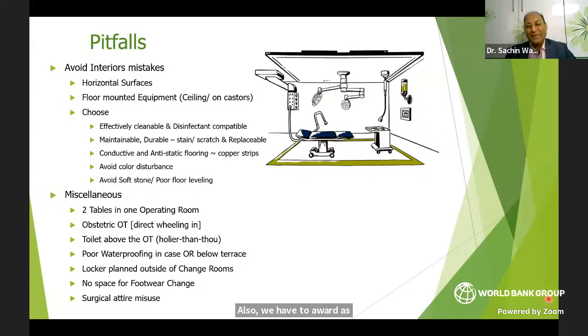We also have to avoid, as much as possible, floor mounted equipment. So primarily all equipment will be either ceiling suspended, like the OT lights or pendants, or on casters like the OT table and trolleys, so that whenever required you could clean the entire floor. That's a favorable thing to have.